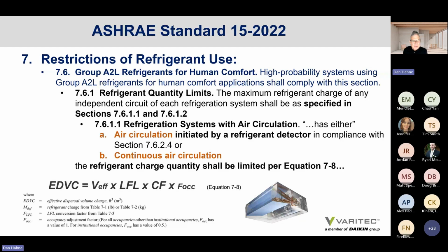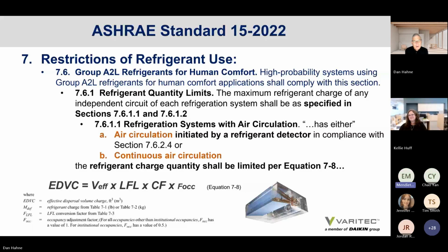But Ed, question, isn't it implicit in the RCL that the LFL has been taken into account based on the refrigerant classification? Yeah, you're looking at the refrigerant type. So if it's R32, you have 19.1. If you have a different refrigerant, that's going to be a different LFL. Unfortunately, I just don't have all of these variables in front of me, but I'm trying not to confuse the audience by saying it's something different. We still are saying this is the amount of refrigerant that's allowed into the space, and you cannot exceed that. It's just that this is for the A2L, and it looks different than the one for A1, which showed the RCL.